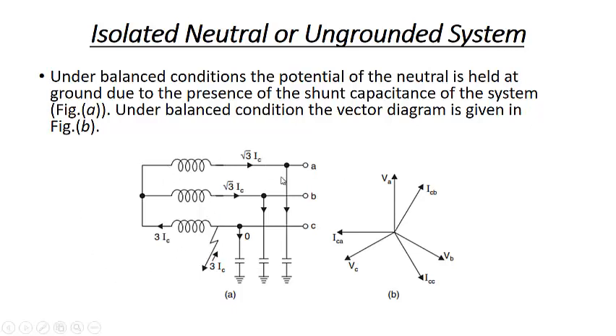This is a schematic diagram of an ungrounded system where the neutral of the system is not connected to the ground or earth. So under normal, balanced conditions, you will see the voltages VA, VB and VC are balanced and displaced from each other by 120 degrees, and the currents also have some phase angle with respect to the respective voltage, and all three currents flowing through the phases are also balanced and displaced from each other by 120 degrees. So this is the isolated neutral, and in case of the neutral grounded system, they will remain the same. The phasor diagram, currents and voltages will not have any difference under balanced and normal conditions.